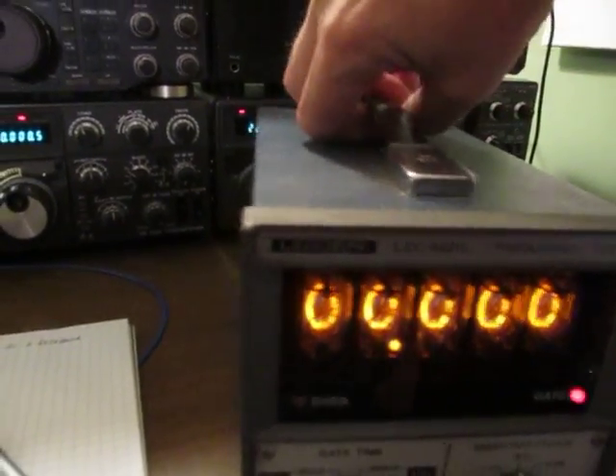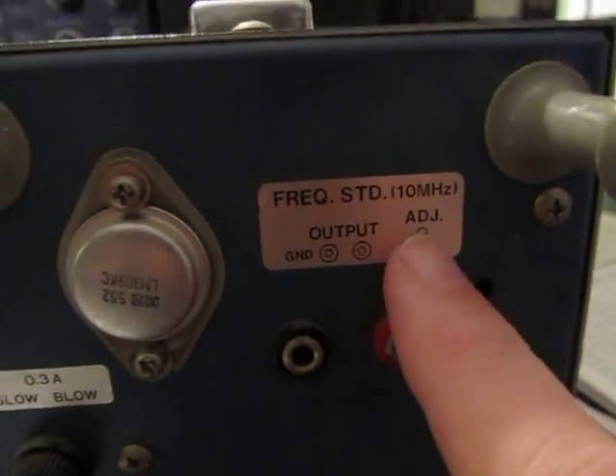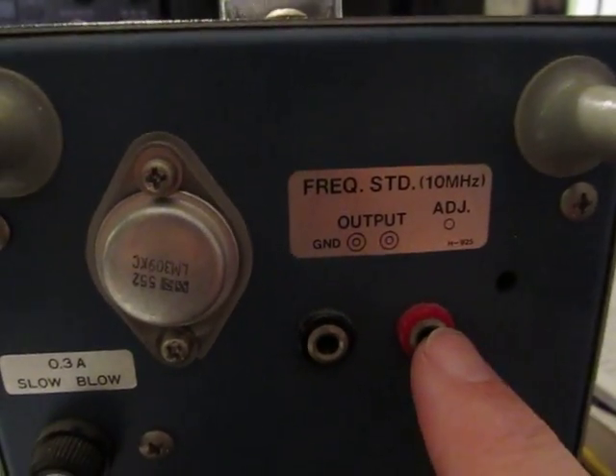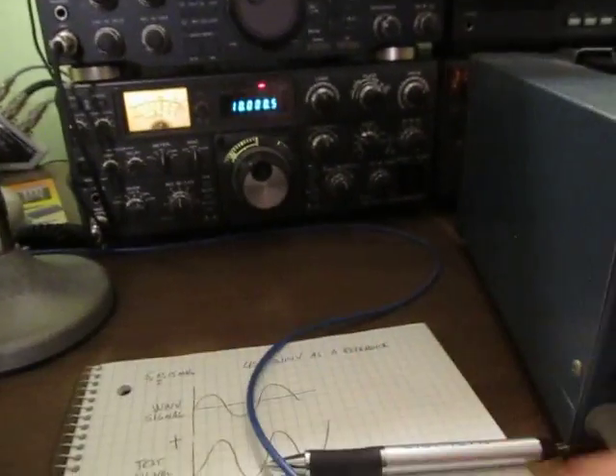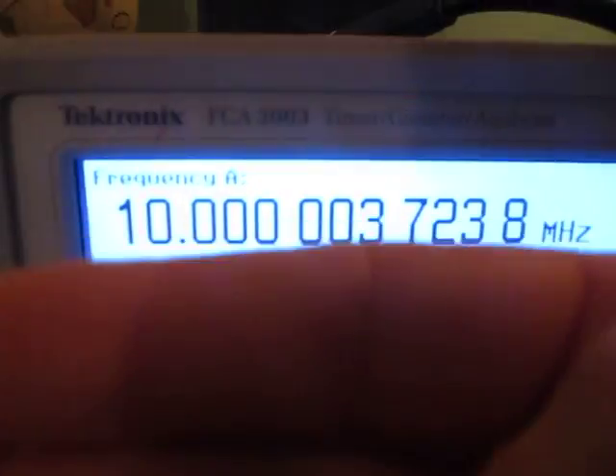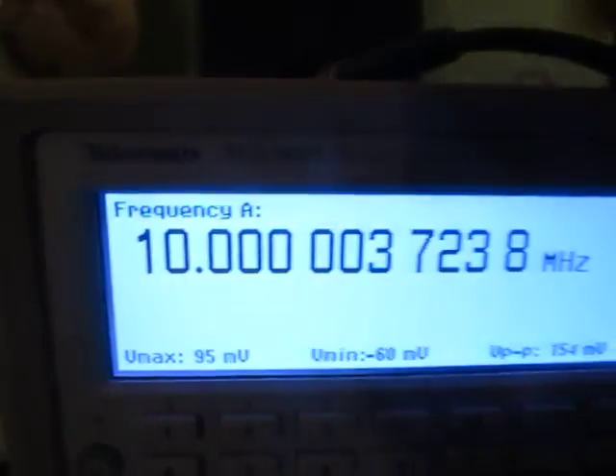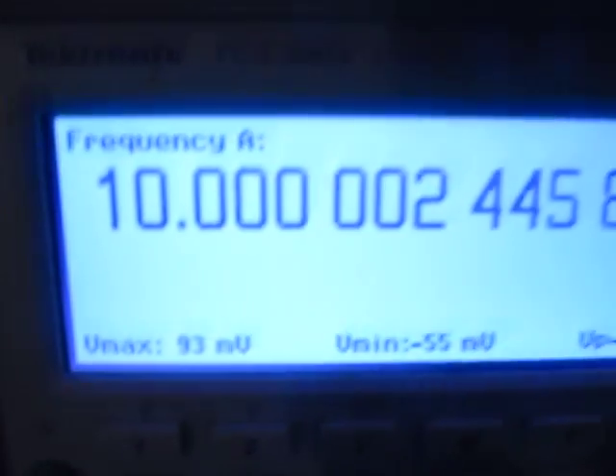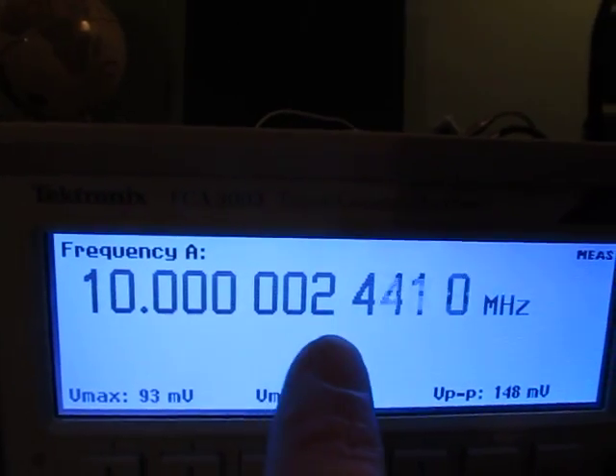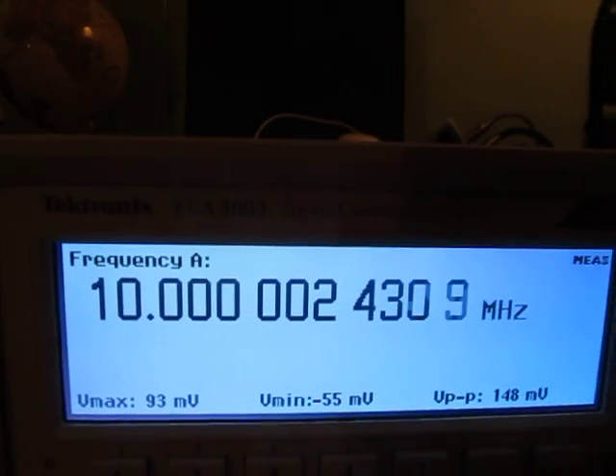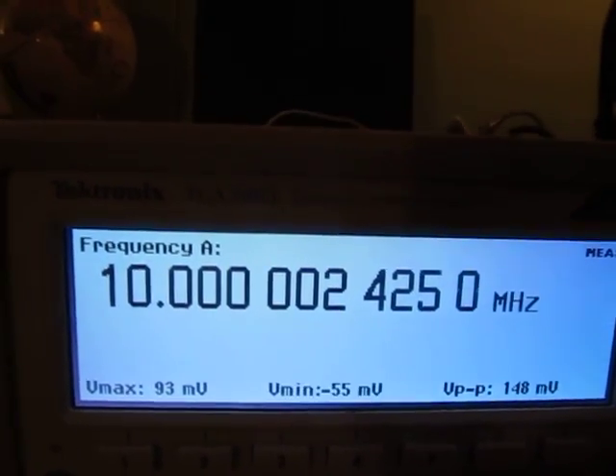Let's take a look at the counter. On the back of the counter I can see there's a frequency standard output — ground and output — at 10 MHz, and there's an adjustment here. I also have a nice Tektronix FCA 3003 frequency counter here that I've coupled in, and I can actually see that this reference is only 2 Hz off out of 10 MHz, which is actually pretty good — that's 0.2 ppm off. So it's only 2 Hz, which means I'll actually be able to hear a beat.